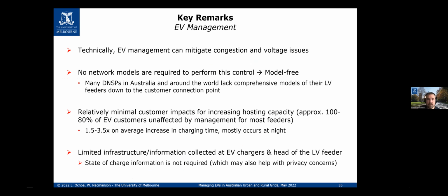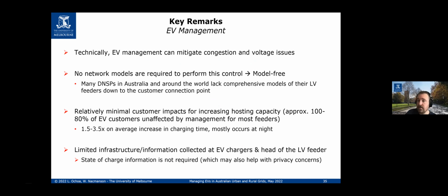So, some key remarks here. Technically, EV management can mitigate congestion and voltage issues. You can do this in theory without a physical model running power flows, if you have sensors at the head of the feeder that can measure the current in the conductor, since that's where the problem is. You can also figure out transformer issues, and you have voltage information from the customers you're managing. You don't need every customer's voltage, only the EV customers'.